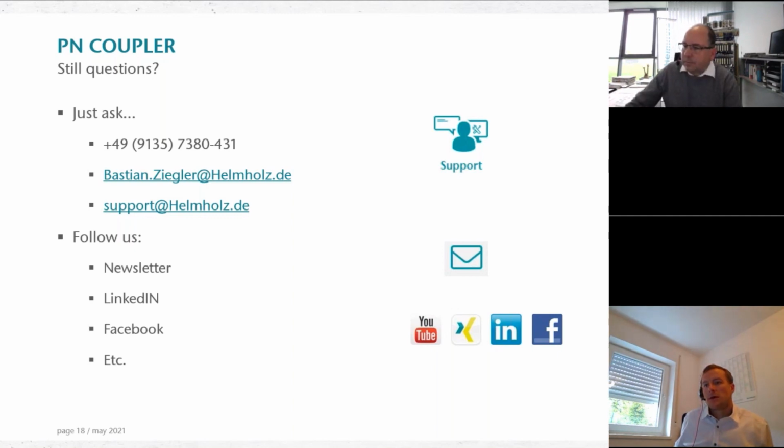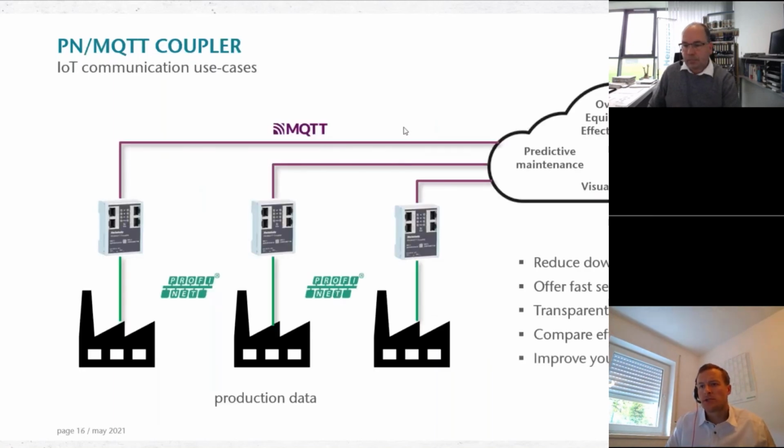Next question. This question is by Mehdi. It pertains to page 16 of the presentation. His question is, could we use an Ethernet switch after the MQTT couplers for collecting data, and then after that use an LTE router for sending? Yeah. So this pink line here for MQTT is just a symbol. The network you have at the end customer doesn't matter. You can have a switch. You should have a router, because the device itself is not a router. You need it at this position.